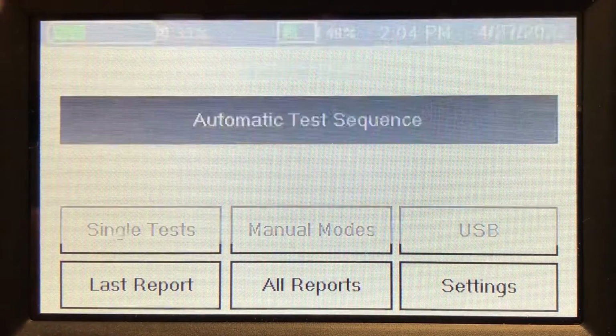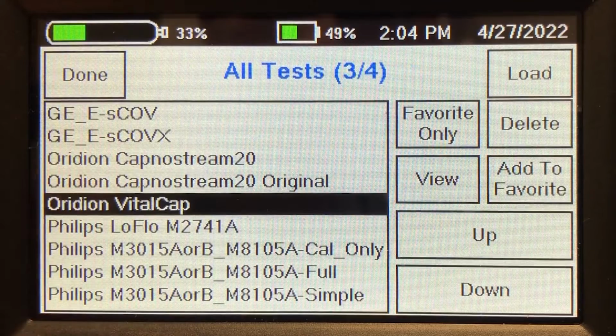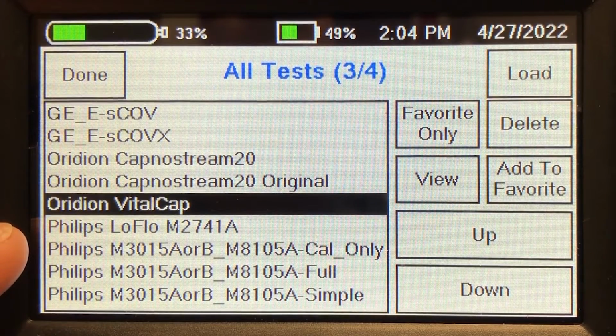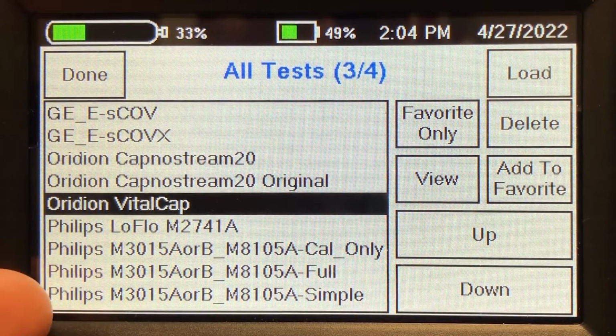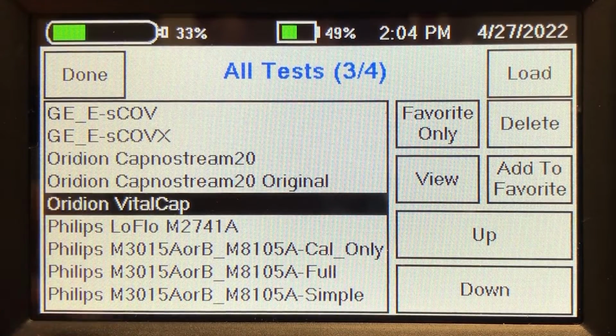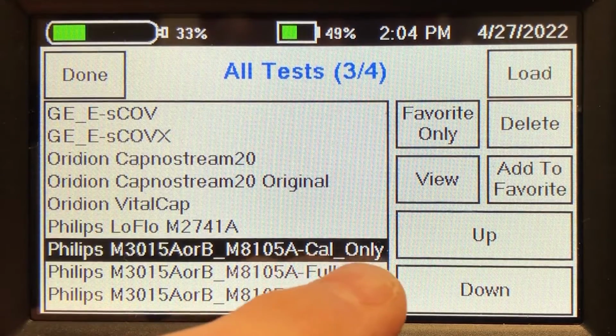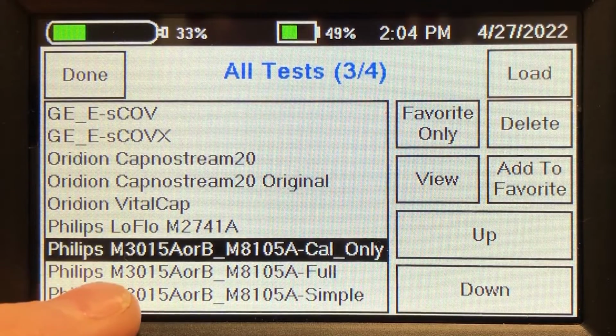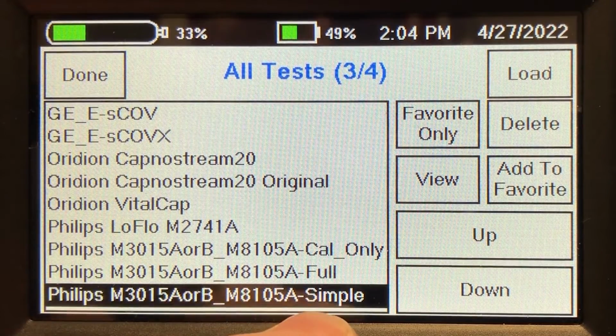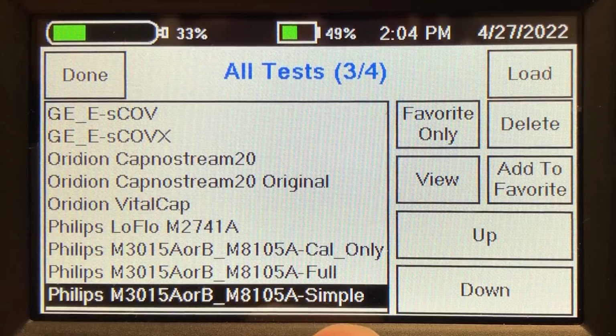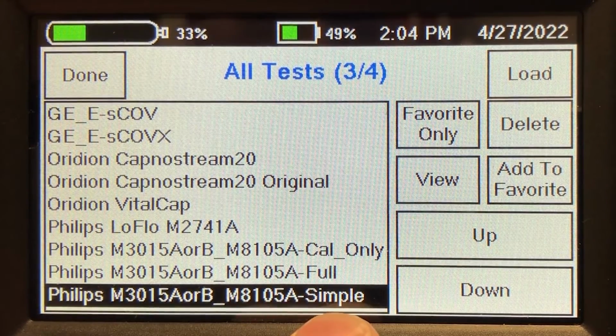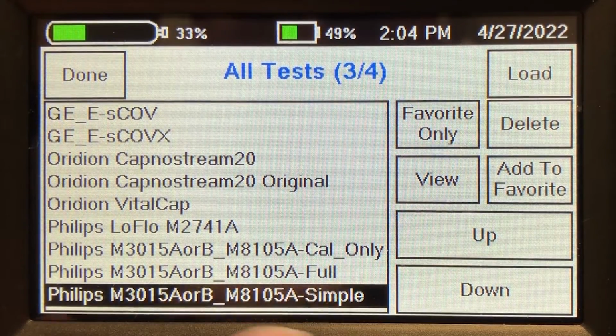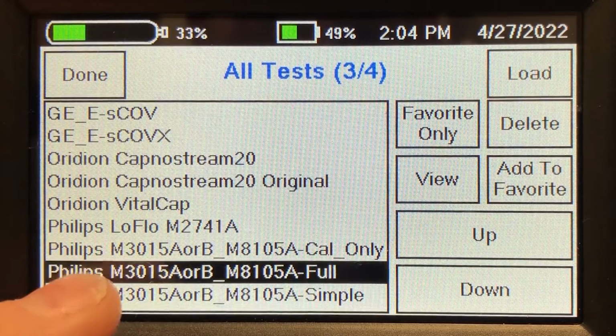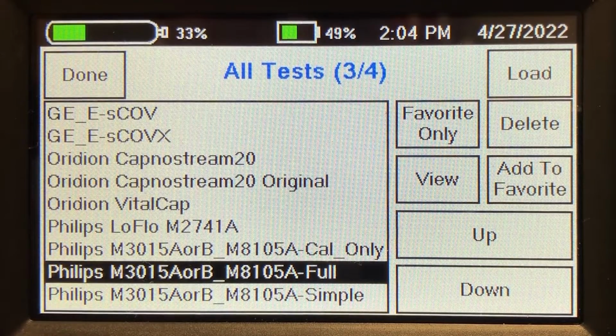Okay, today I'm going to show you how to test a Philips 3015A or 3015B module. You see we have three different test sequences here. One of them is calibration only, it just does the cal steps. Simple is basically the full manufacturer's recommended routine, only it uses our quicker leak testing method, and it doesn't include the span gas check with 10% CO2, it just does the calibration with 5% CO2. And then there's the full, which is the full manufacturer's recommended routine.